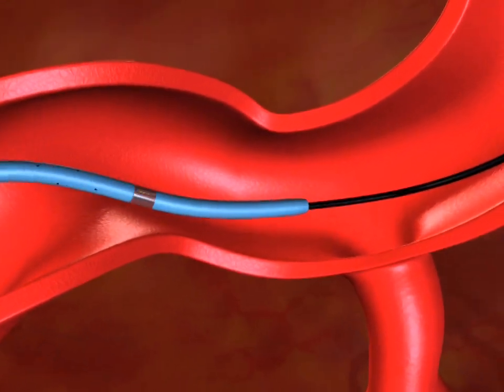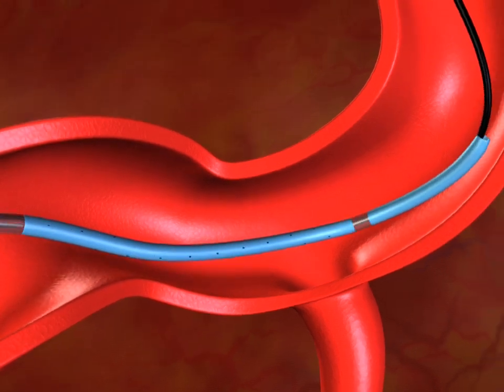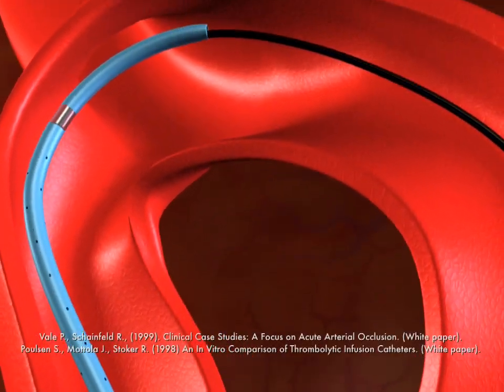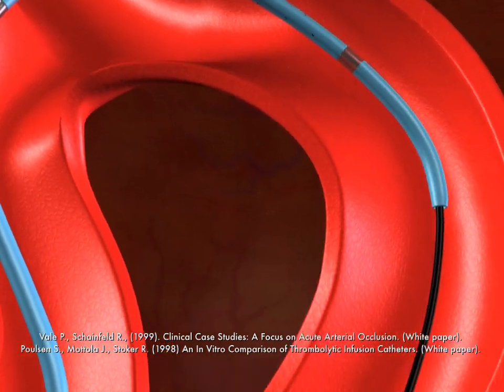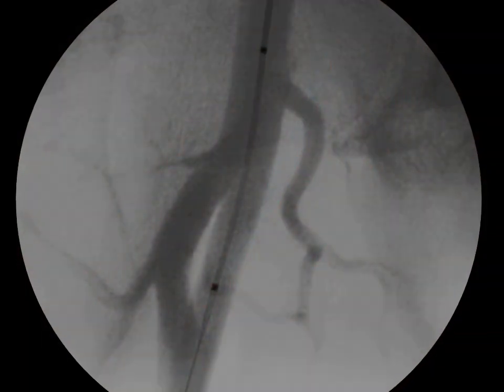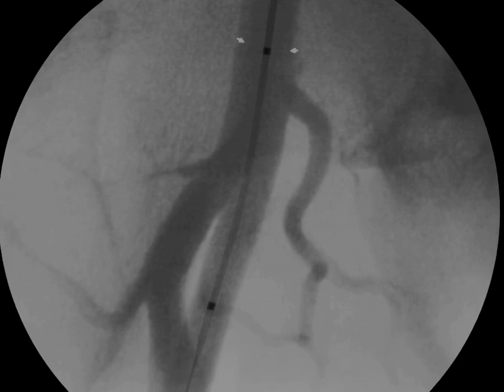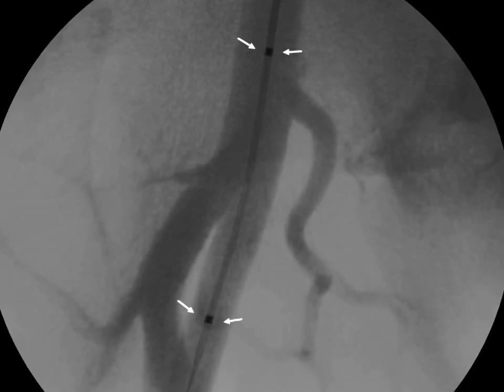Both 4 and 5 French Merit Medical systems can be placed over a standard 0.035-inch guide wire and have been reported in the literature to cross with ease.